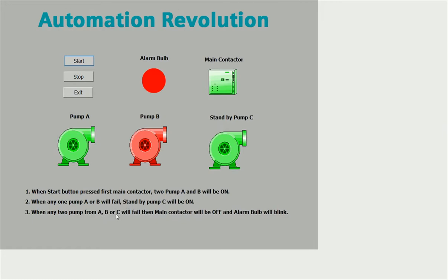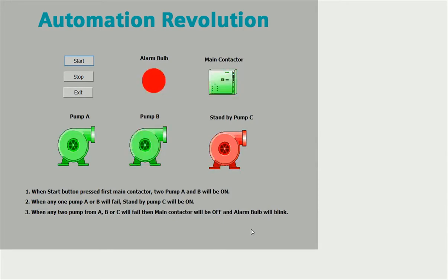As per the third condition, when any two pumps from A, B, or C fail, the main contactor will turn off and the alarm will come on. When two pumps from ABC fail — for example, both A and B — the main contactor will turn off and the alarm bulb will blink, giving an indication that only one pump is running. Similarly for other combinations. For this logic, we have developed a ladder diagram using the memory bit concept.